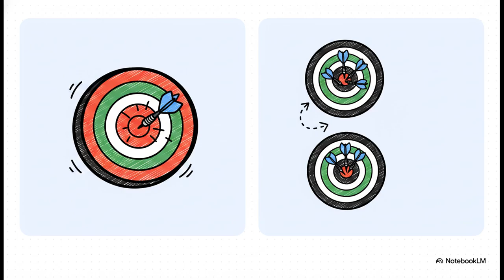Think of it as hitting the absolute dead center of the bullseye. Precision, or repeatability, on the other hand, is the ability to consistently provide the same measurement under the same conditions. You can be highly repeatable, hitting the exact same wrong spot ten times in a row, without actually being accurate. Interestingly, in manufacturing, repeatability is often prized first, because if a machine is at least repeatable, you can mathematically adjust it to become accurate later.